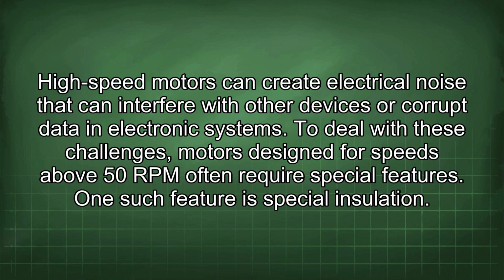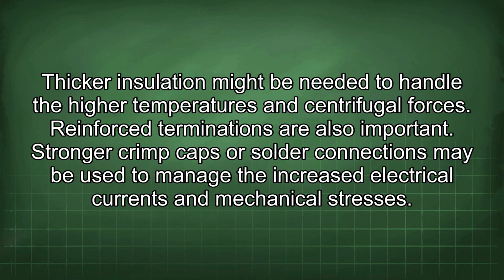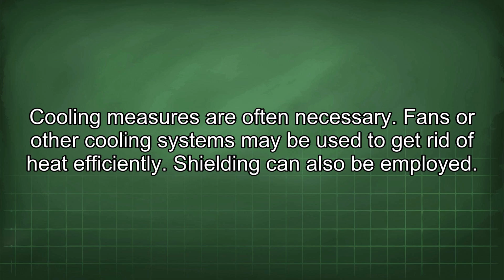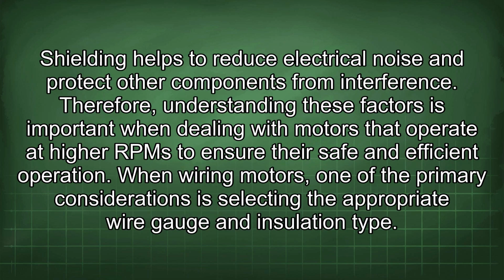To deal with these challenges, motors designed for speeds above 50 RPM often require special features. One such feature is special insulation. Thicker insulation might be needed to handle the higher temperatures and centrifugal forces. Reinforced terminations are also important. Stronger crimp caps or solder connections may be used to manage the increased electrical currents and mechanical stresses. Cooling measures are often necessary. Fans or other cooling systems may be used to get rid of heat efficiently. Shielding can also be employed. Shielding helps to reduce electrical noise and protect other components from interference. Therefore, understanding these factors is important when dealing with motors that operate at higher RPM to ensure their safe and efficient operation.